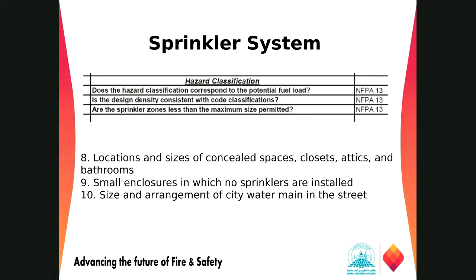The ones we discussed in NFPA 13 while discussing fire protection too. So the first one we have to look at: does the hazard classification correspond to the potential fuel load? What is the load, and based on that they have selected the fire hazard. The second one, is the design density applicable for that hazard, the one from the curve we saw? And are the sprinkler zones less than the maximum size permitted?